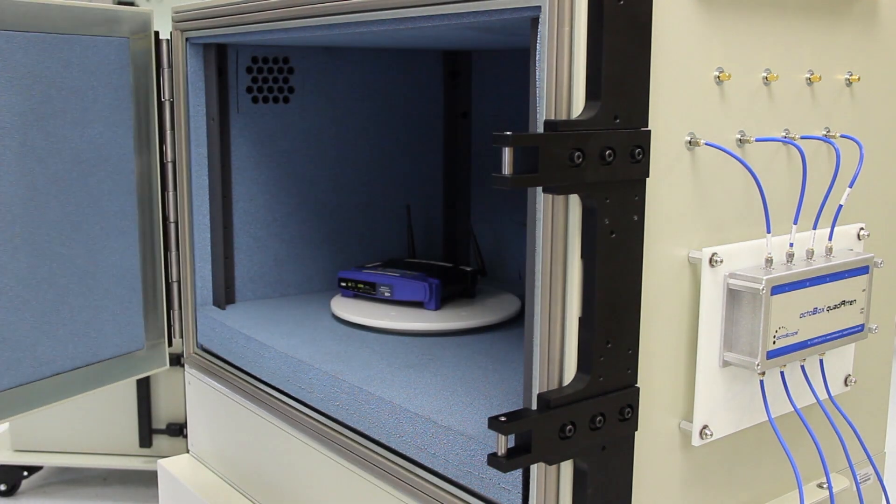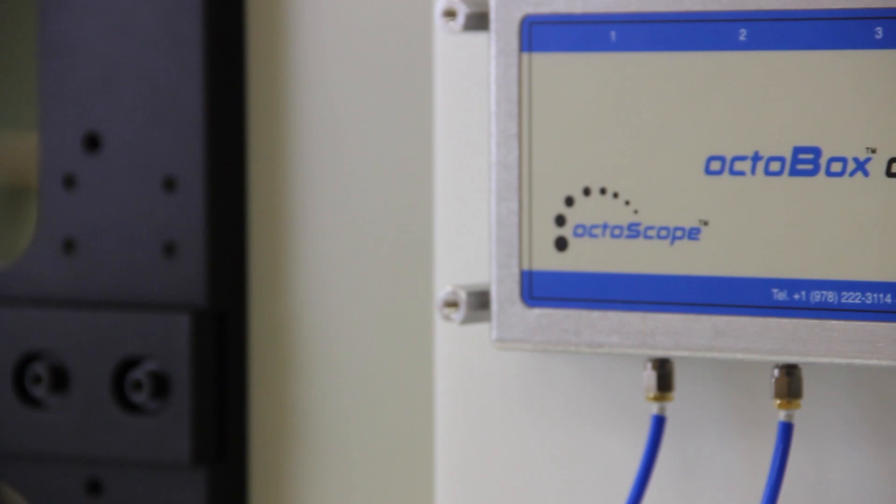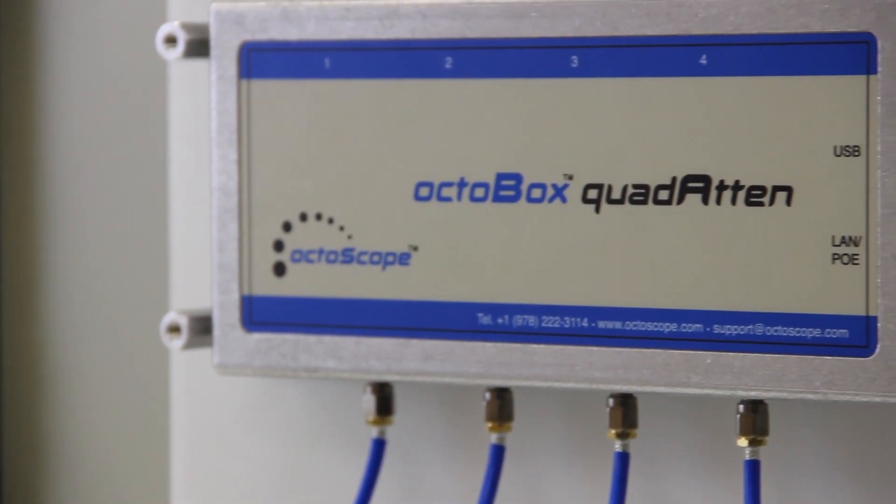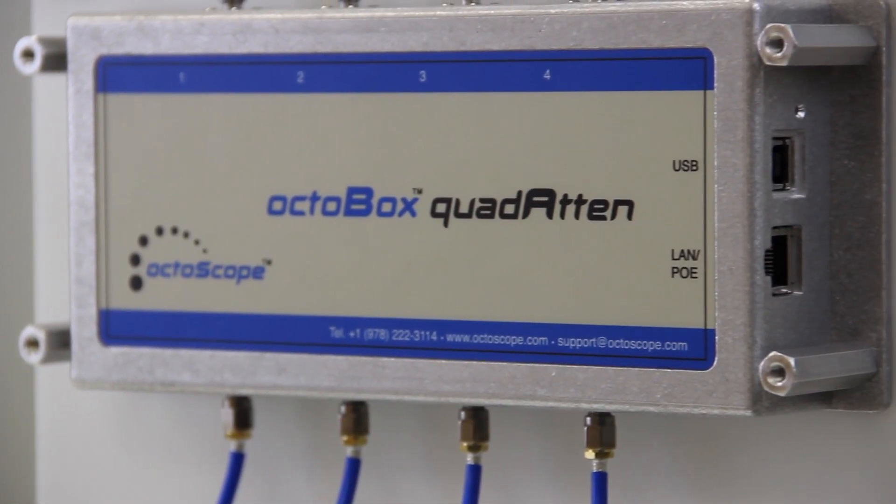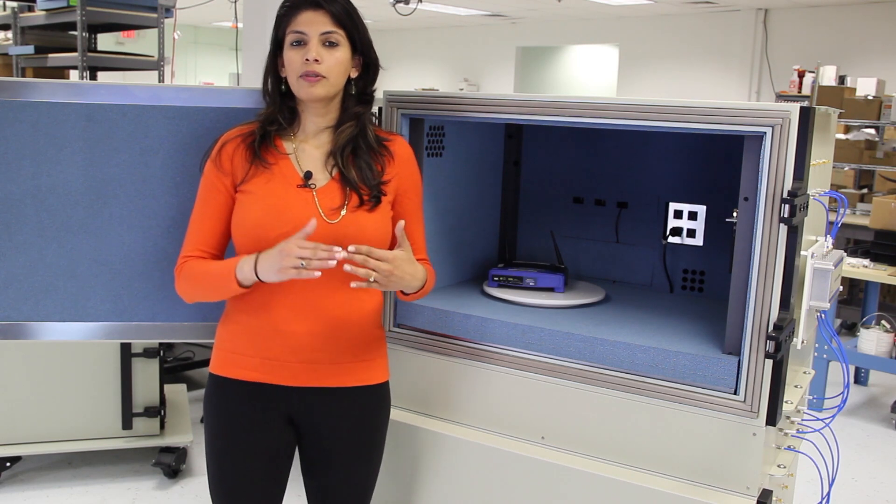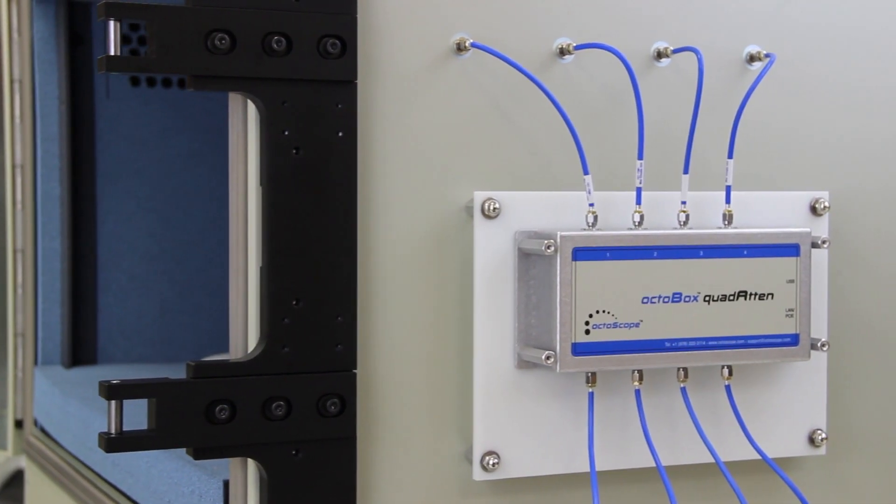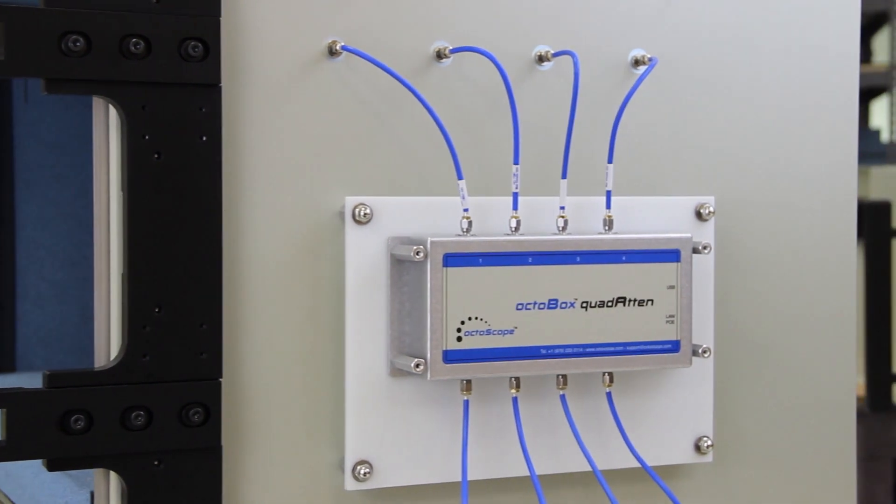Each of the 4 attenuators in a module can be independently controlled or programmed via USB or Ethernet. The attenuator range from 0 to 63 dB with steps of 0.5 dB provides an accurate and broad sweep of receiver dynamic range down to the lowest levels.